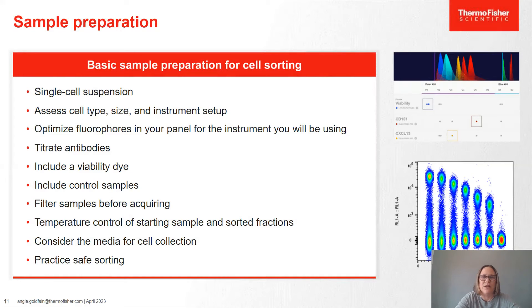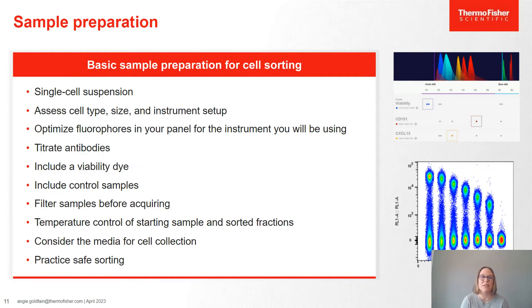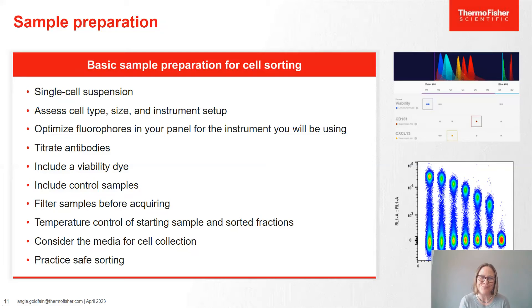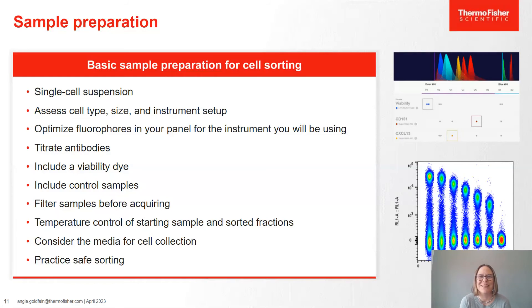Sample preparation is really key to cell sorting. No matter the instrument you're using, there are basic guidelines. Single cell suspension is really, really important — we're pushing the sample through a nozzle or small orifice, and clumps of cells will clog that orifice. Clogging is something we'd like to avoid as much as possible, so do as much as you can to achieve a single cell suspension. Always filter samples to remove any clumps or residual particles from the prep.